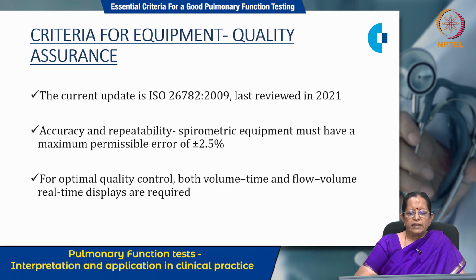Next, coming to the criteria for equipment. That is the quality assurance for the equipment. This current update is ISO 26782-2009, which was last reviewed in 2021. This spirometric equipment must have a maximum permissible error for accuracy and repeatability of plus or minus 2.5%. For optimal quality control, both volume time and flow volume real time displays are required.